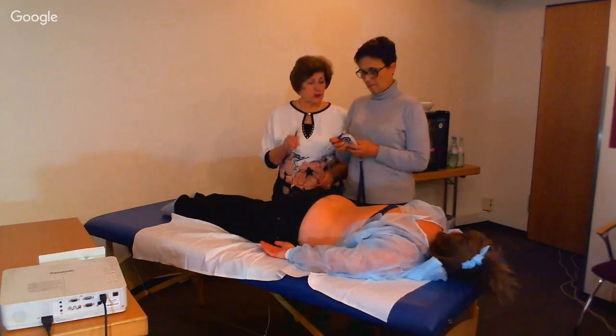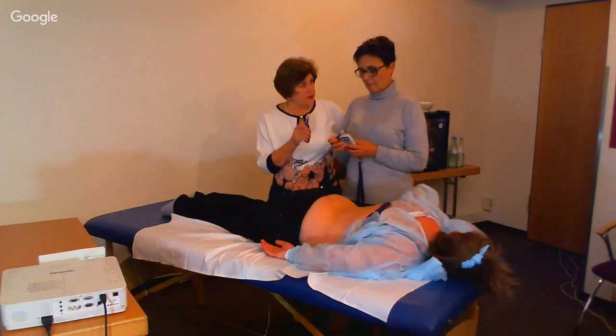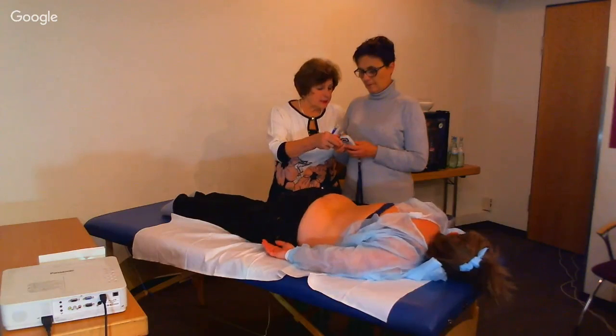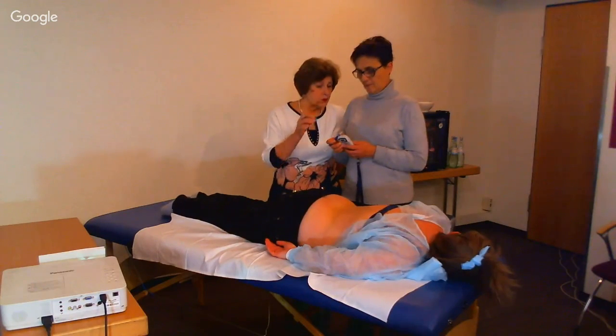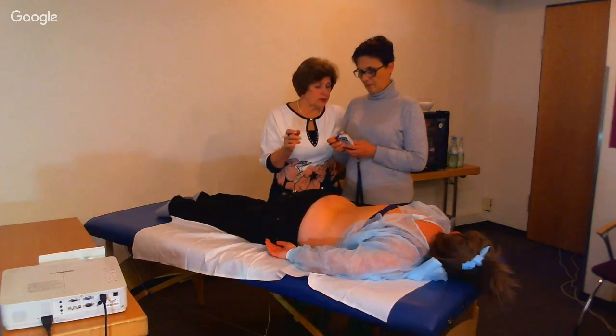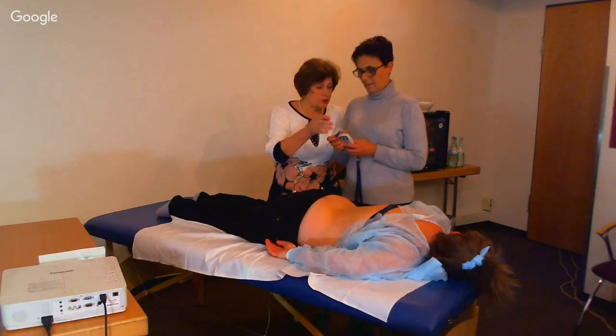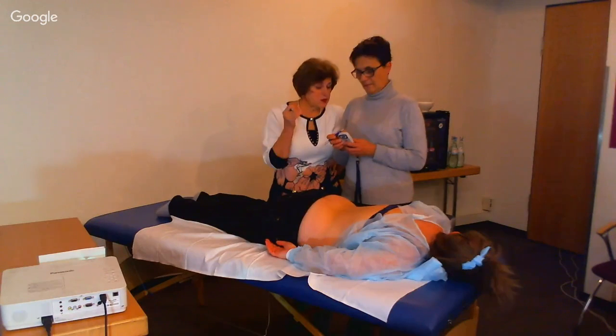But before we start working, you need to set diagnostics to D1 again. Choose D1 mode. Remove amplitude modulation: press minus here while it is lit. Then remove the frequency modulation, minus. Now call up diagnostics.